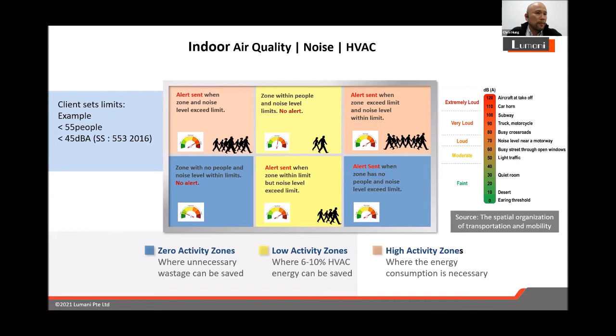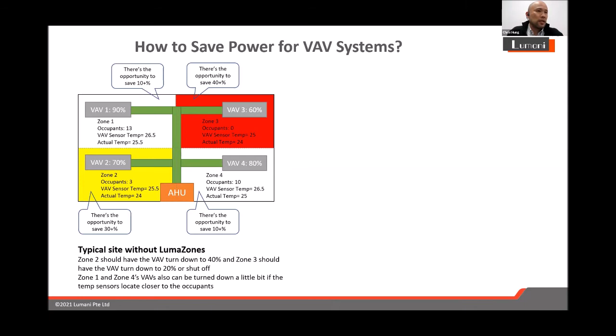HVAC system is the most power consuming equipment inside the building. Now we are going to talk about VAV, how we save energy there. In the typical zone, typical space with 4 zones, you have some zone with people, some zone without people. Take this for example, the red zone is empty, but it still blows cold air there, and the valve is open like 60%. It's a waste there. So what can we do there?